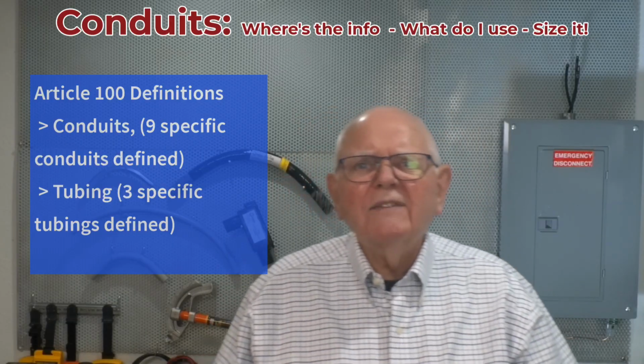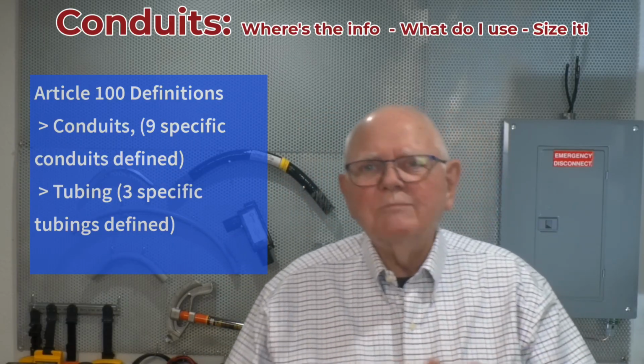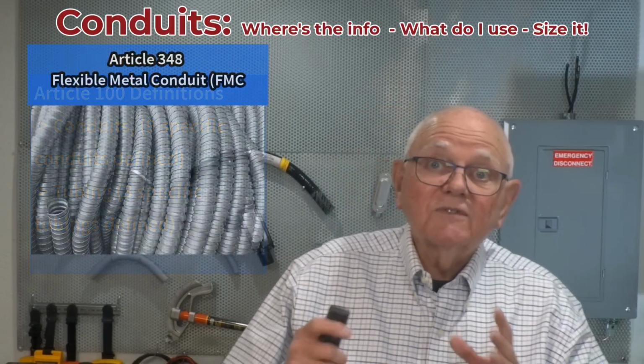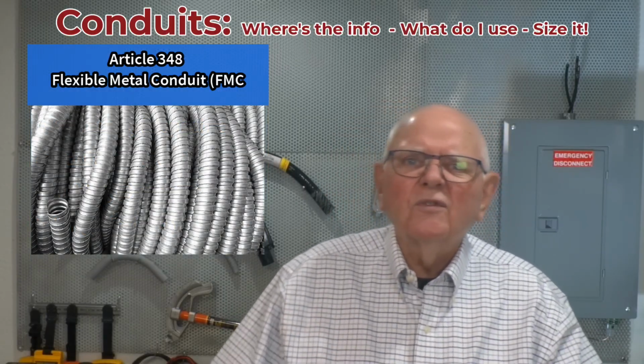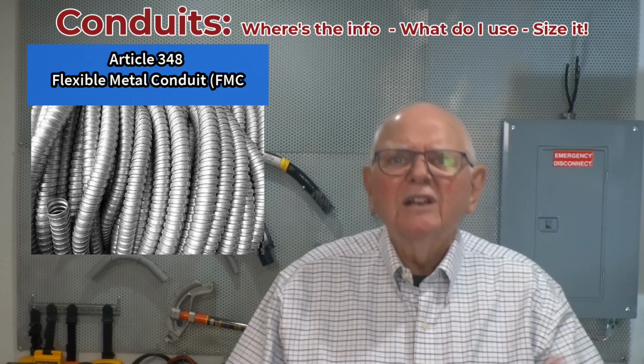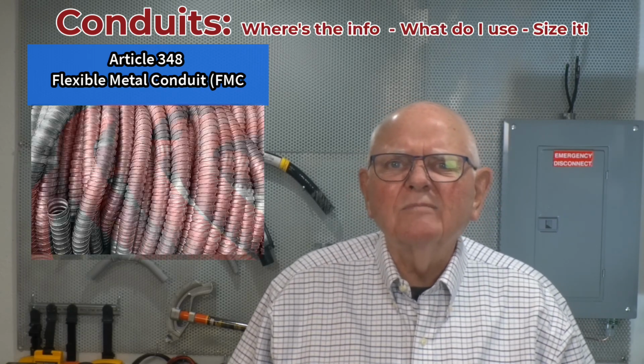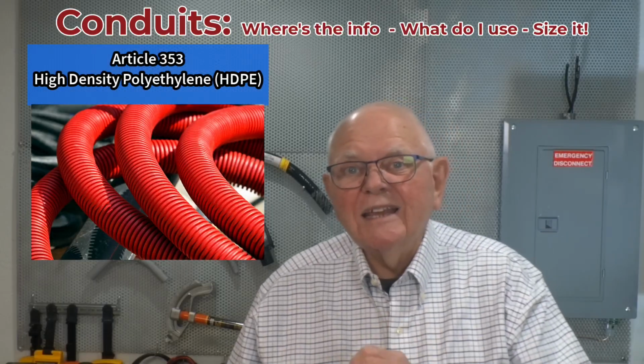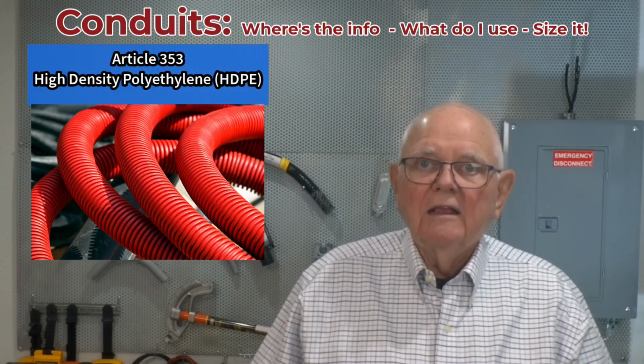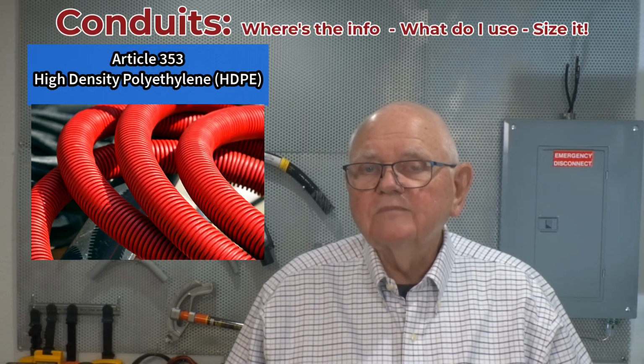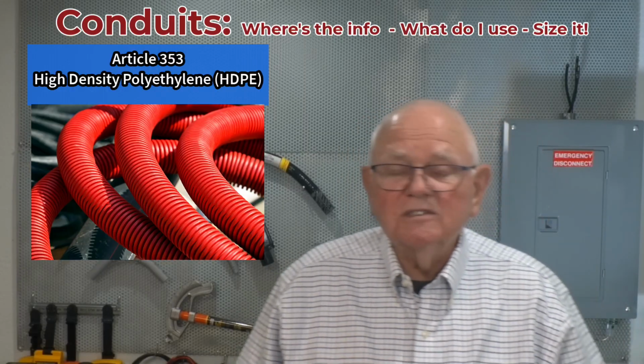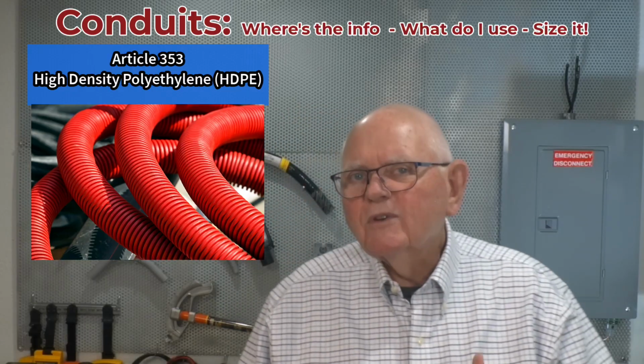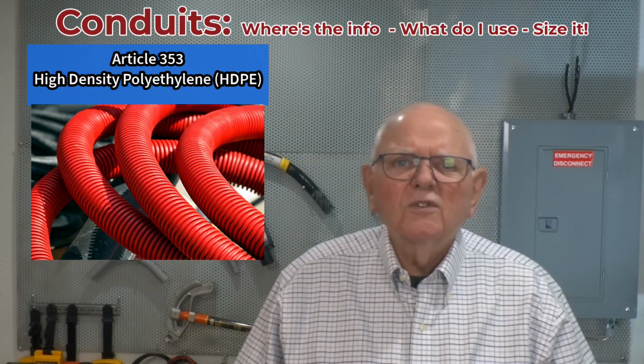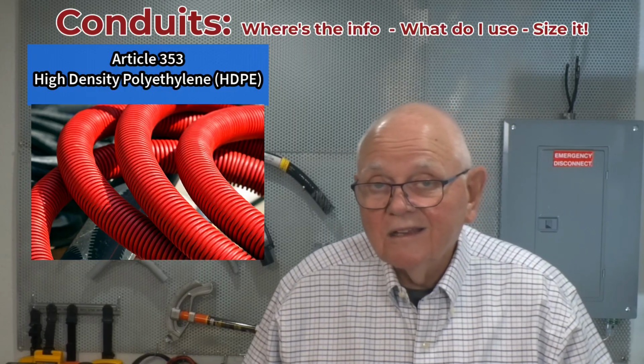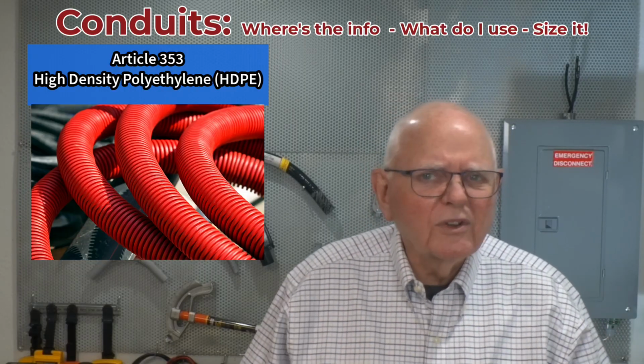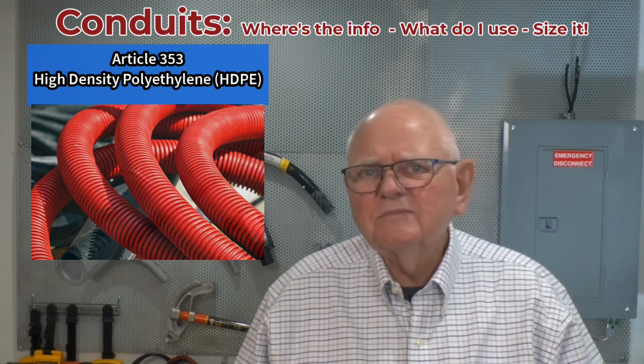So anyway, if I look at these definitions, pretty much the same, but a little bit different, obviously. For instance, flexible metal conduit: helically wound, formed, interlocked metal strips. Okay, flex, right? Flexible metal conduit. Conduit, high density polyethylene, HDPE. It tells us it's a non-metallic raceway, and it's typically used, in direction. It doesn't really give us all this in the definitions. But where do we find this HDPE? Well, typically used for directional boring, like you see in the image there. We use it a lot for communication wiring. You see it installed today.